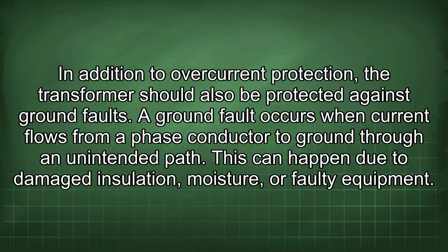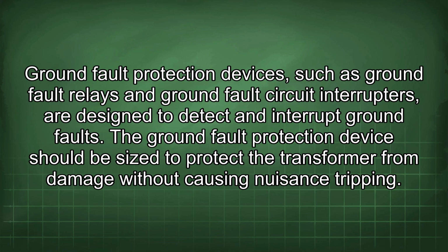In addition to overcurrent protection, the transformer should also be protected against ground faults. A ground fault occurs when current flows from a phase conductor to ground through an unintended path. This can happen due to damaged insulation, moisture, or faulty equipment. Ground fault protection devices, such as ground fault relays and ground fault circuit interrupters, are designed to detect and interrupt ground faults. The ground fault protection device should be sized to protect the transformer from damage without causing nuisance tripping.